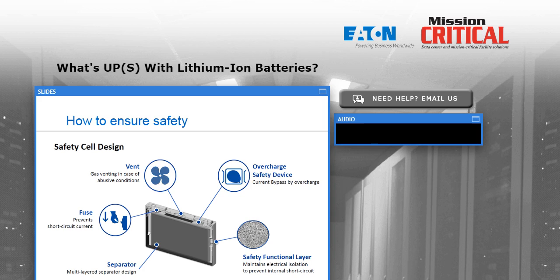There's also an overcharge safety device. This is like a little bypass relay that's built into every single battery. So that gray box that had 8 batteries we saw on a previous slide, every one of those 8 has its own bypass device that's controlled by the management system. So if that battery starts to get a little warm, we're going to reduce the charge current to that battery and do it automatically. If it continues to get warm, we're simply going to bypass it so that it is no longer in the circuit. So effectively taking that battery out of the picture. In addition, each battery contains an internal fuse, so if our electronic controls fail and the current gets too high, the fuse will isolate the battery for us.